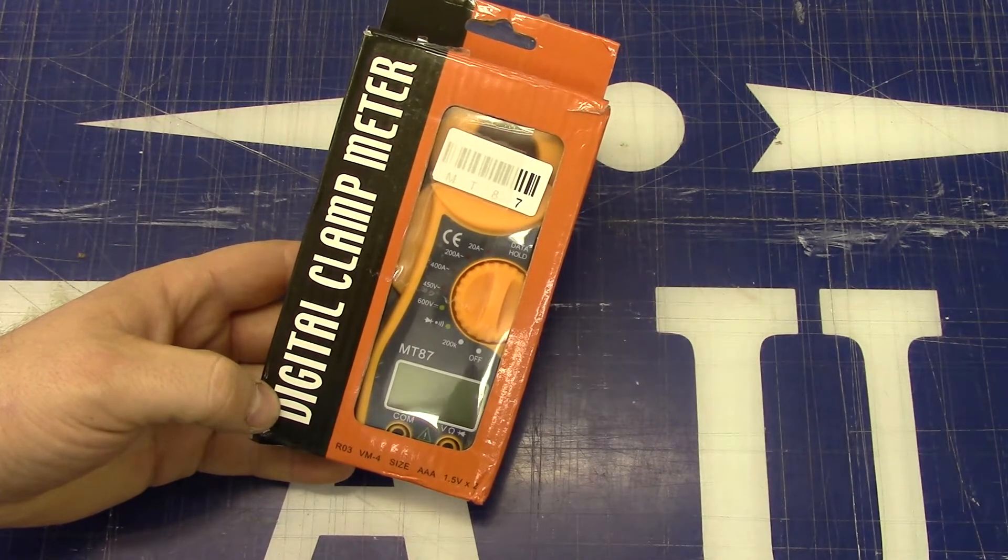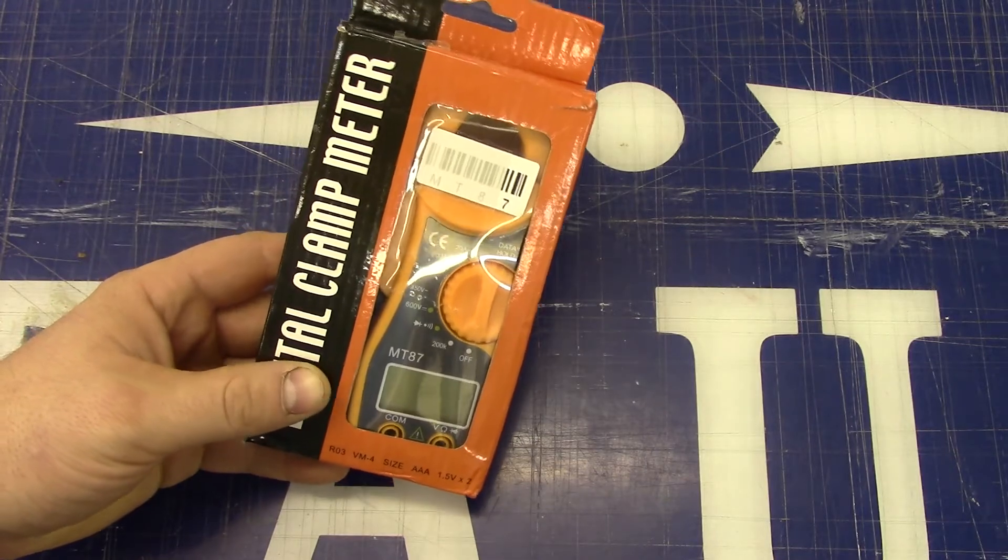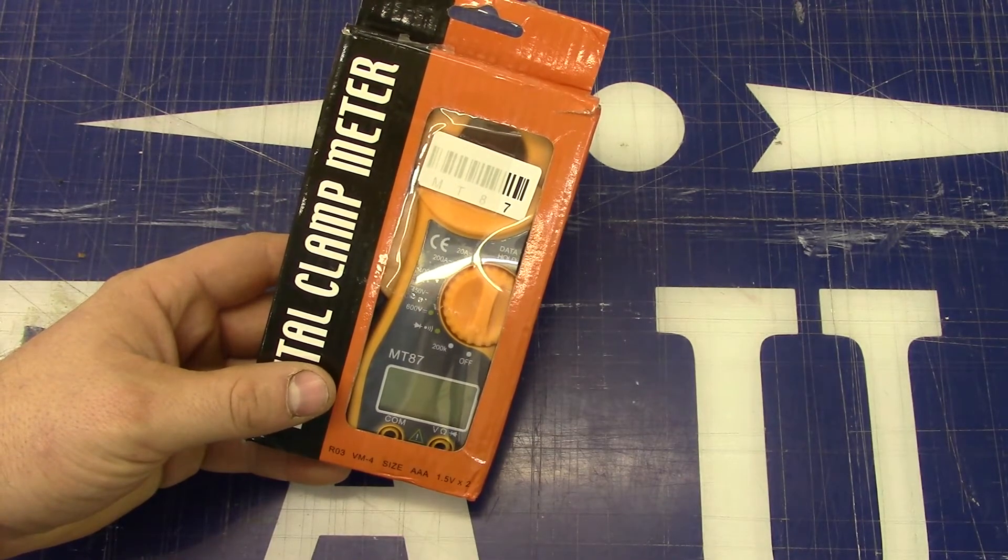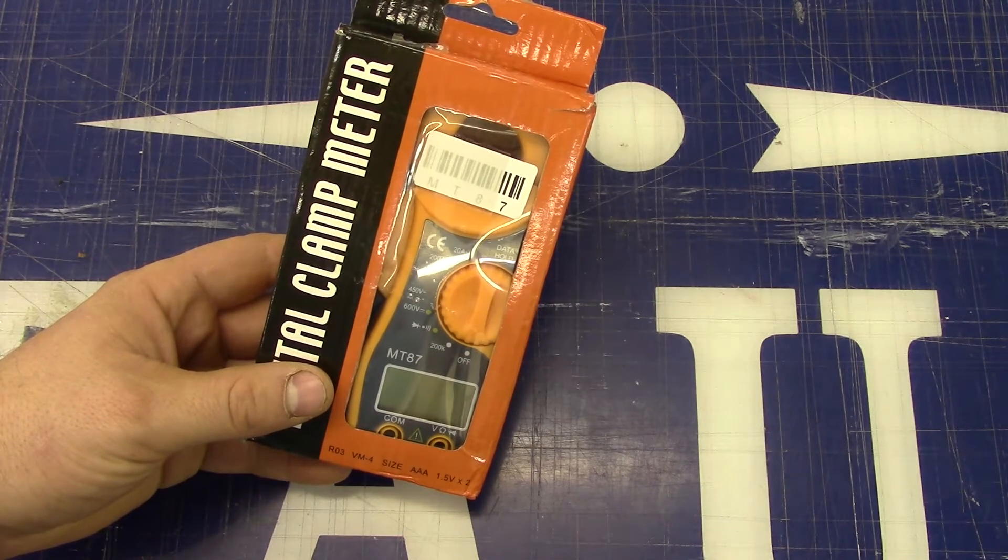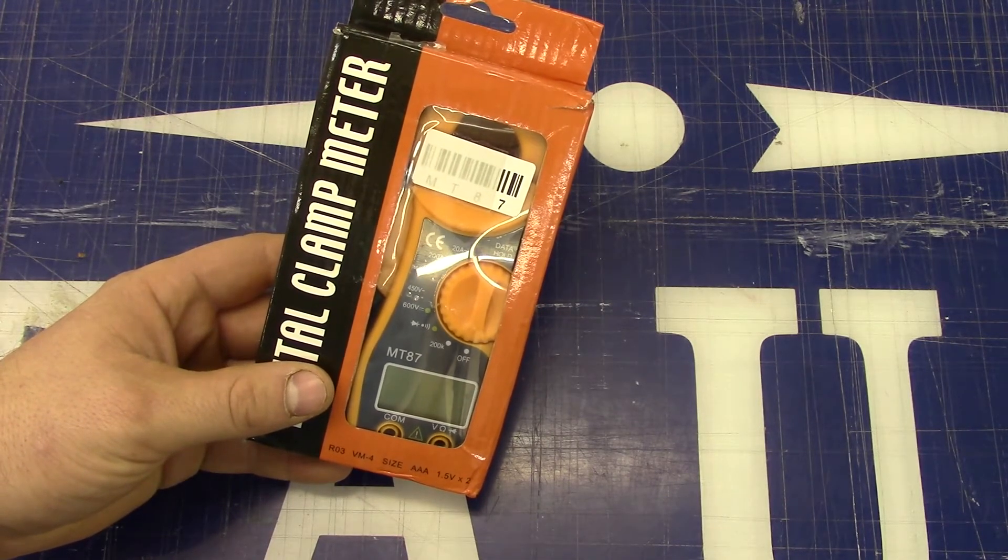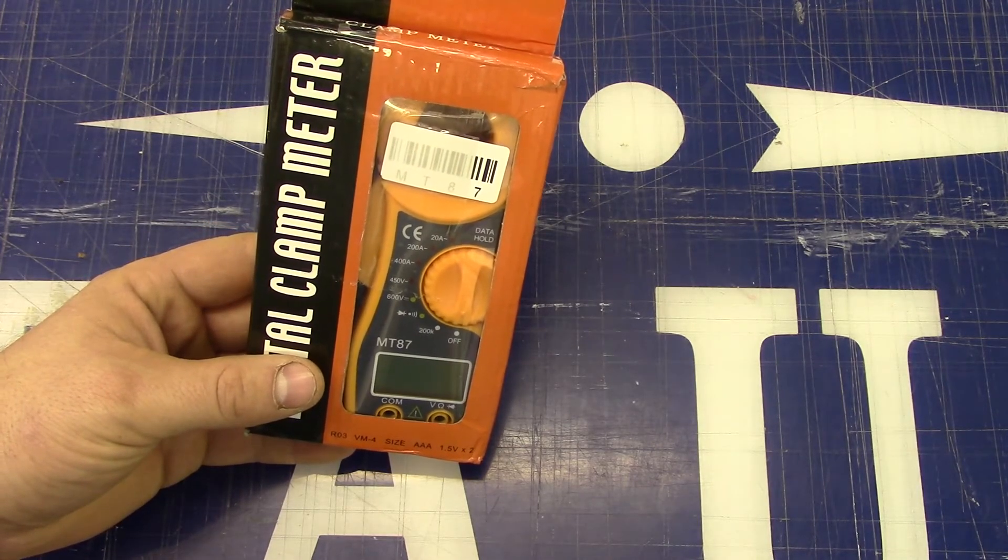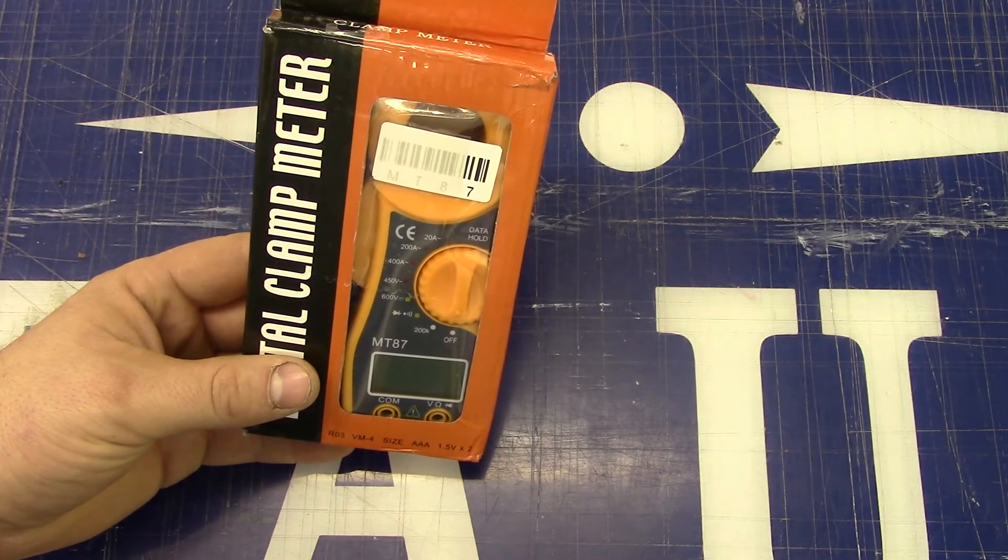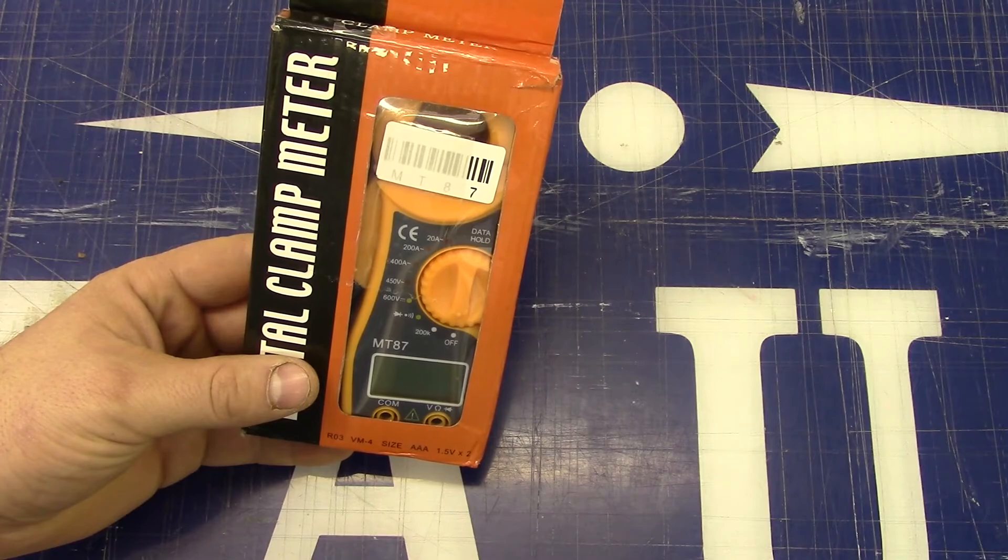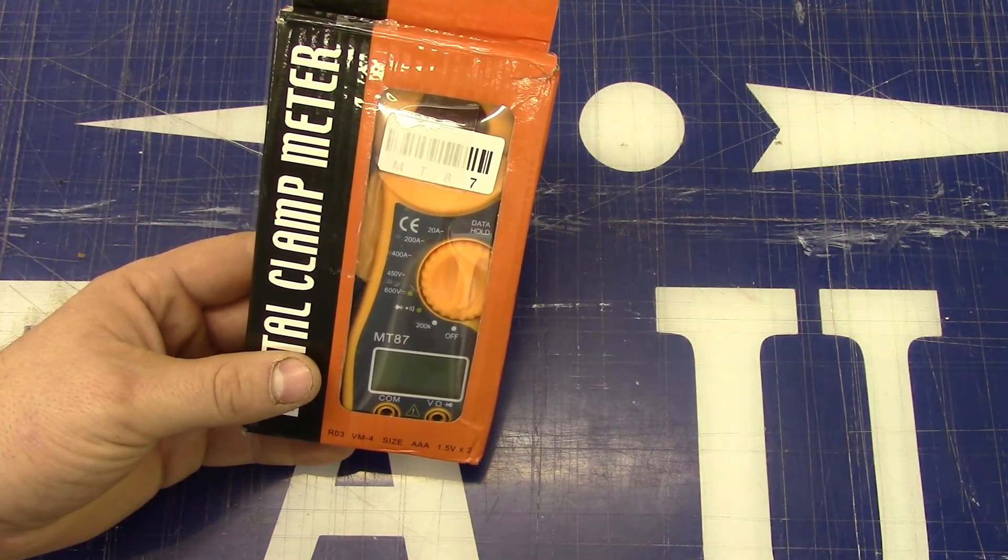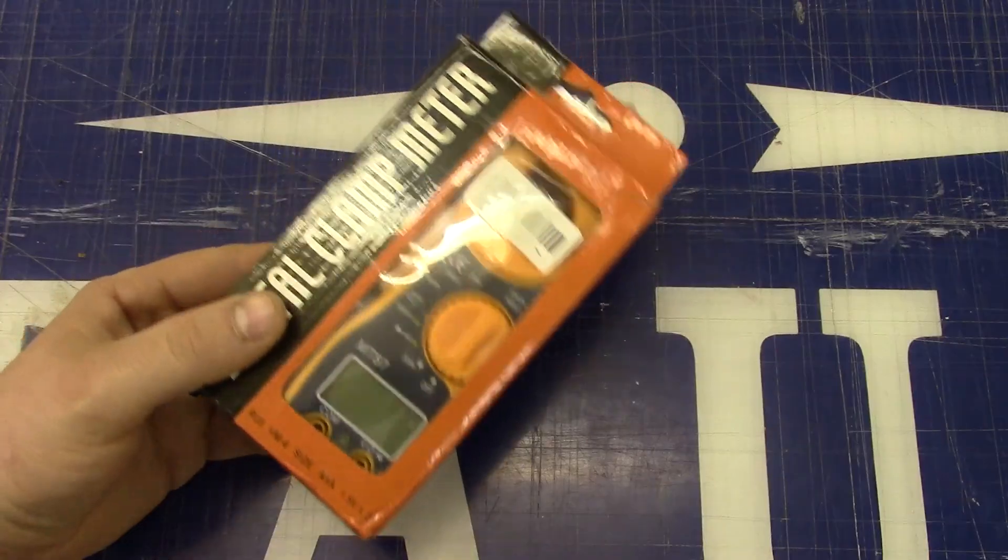Seeing as how it uses a current transformer, just in case you don't already know, that means it only works with AC current. It's not a hall-based sensor, which some of the more expensive amp clamps have and will measure DC current. This one won't. It only works with AC. The voltage doesn't matter. It's a current transformer. It needs an alternating current. But voltage isn't important. Just the current running through the wire. Until next time.